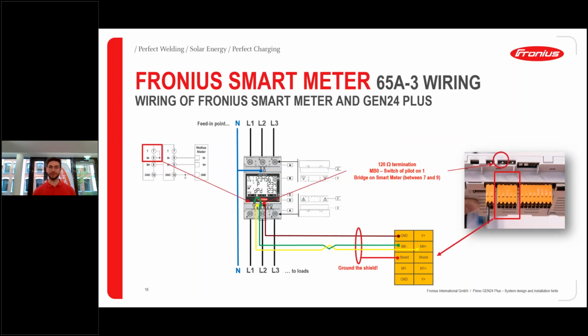Yeah, and one necessary product is, like we can see here, the Fronius smart meter. It's really not an option, it's a necessity to have a Fronius smart meter installed when you want to have a full backup solution. And the Fronius smart meter, so unfortunately I have picked out here a 3-phase smart meter, but there is also a single-phase smart meter available, and it's the same cabling. The process is exactly the same. I will just explain it on behalf of this product here, the 65 amp 3-phase, and there is also a 100 amp single-phase one, which is very suitable, of course, for the Primo GEN24.